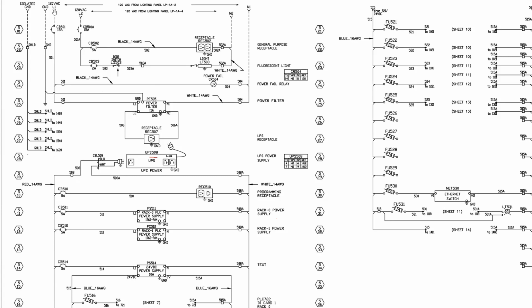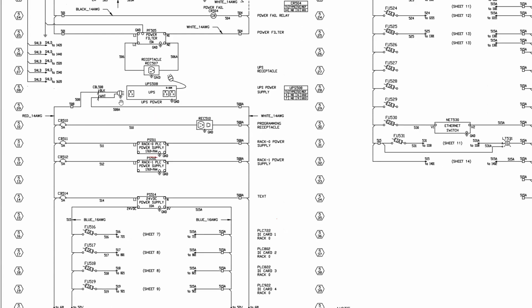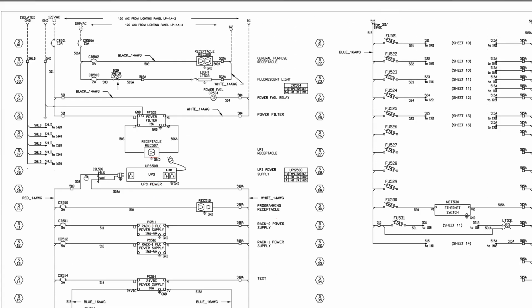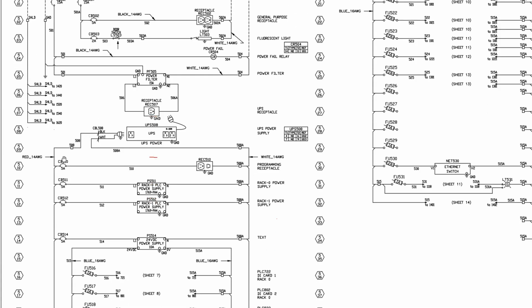But if you were to drop L1, by drop, I mean if you were to open this breaker, as long as the UPS were powered and charged, you would not lose 120 volts here. So it will stay on. You can see down here we don't have a main breaker off of the UPS. Typically you would like to see a main breaker here.